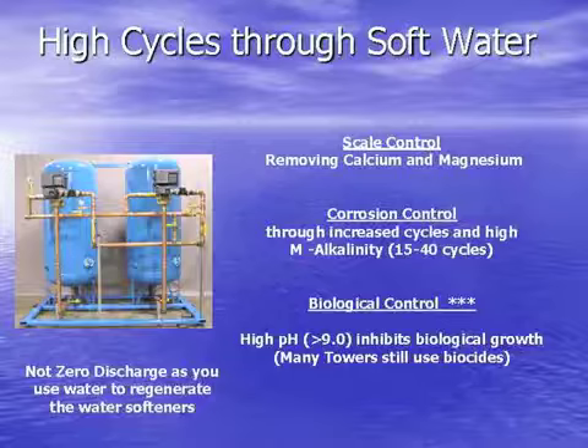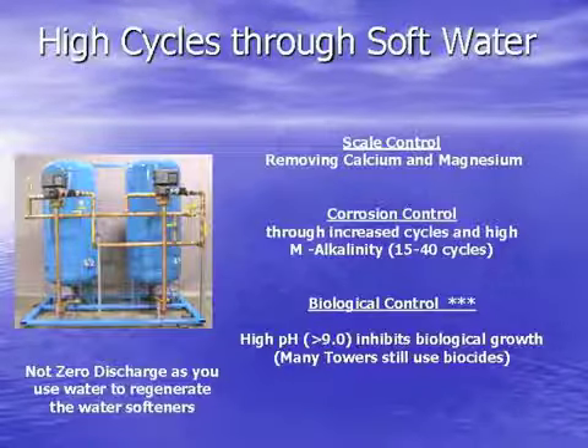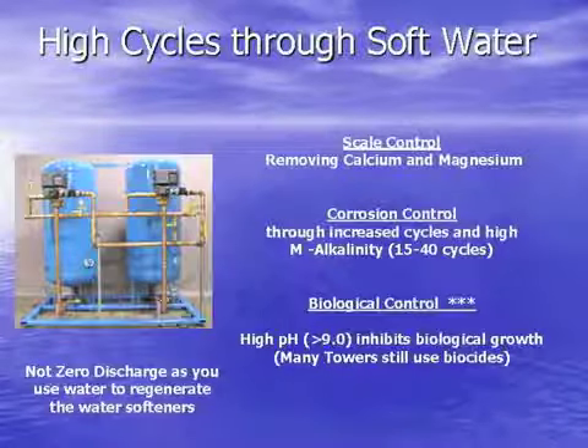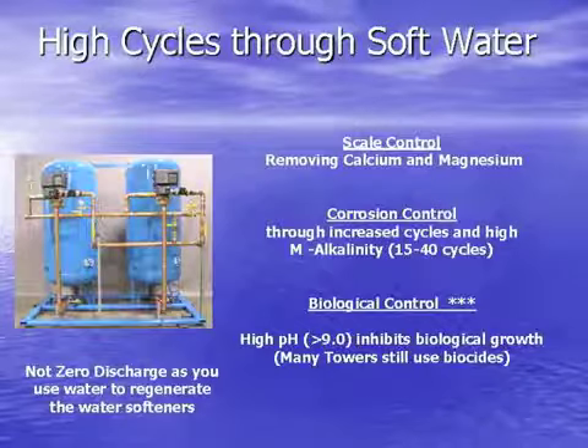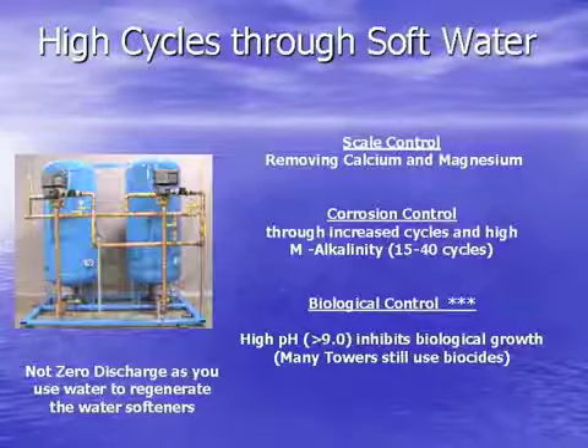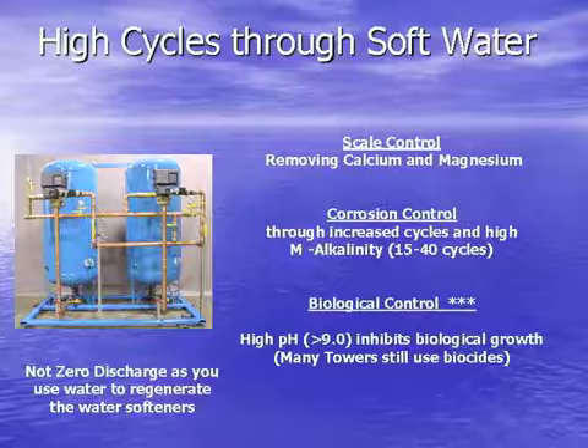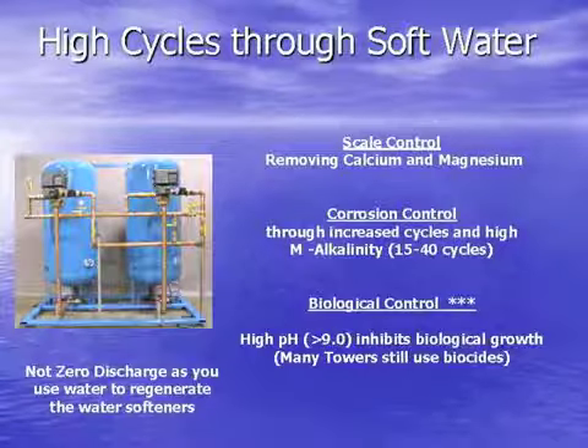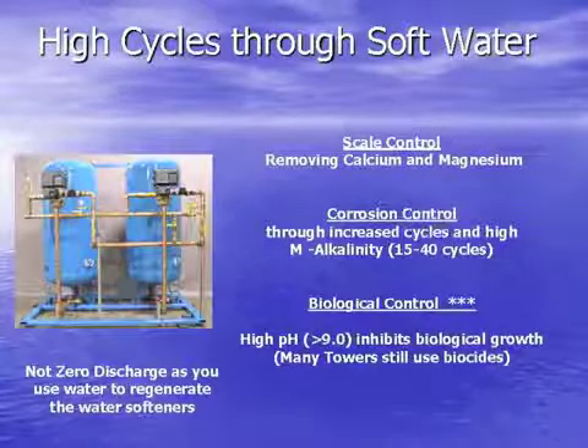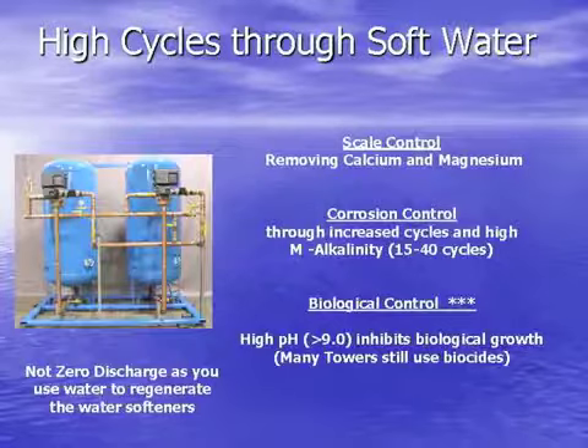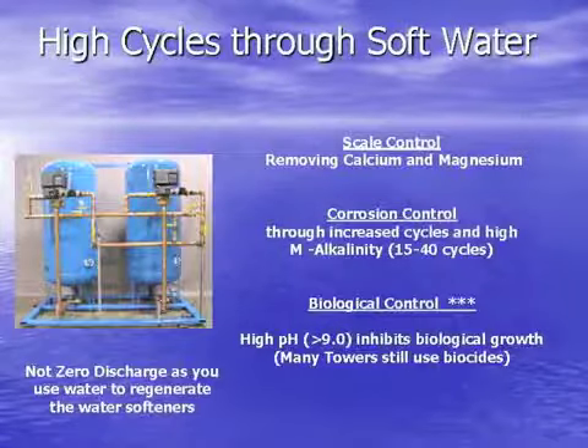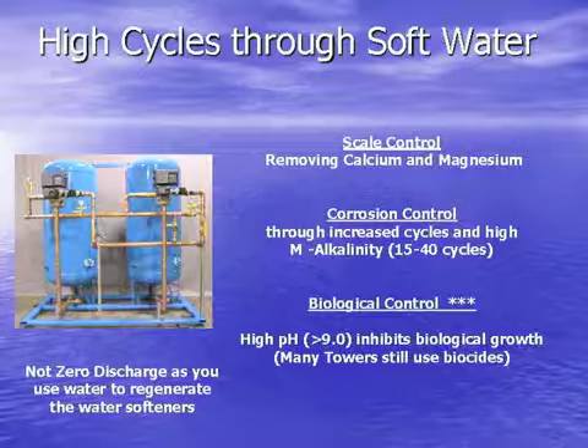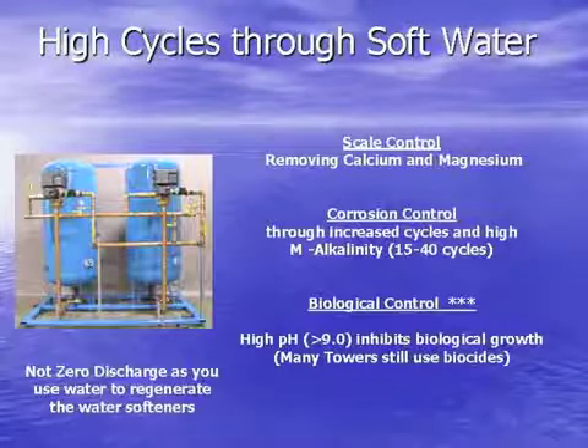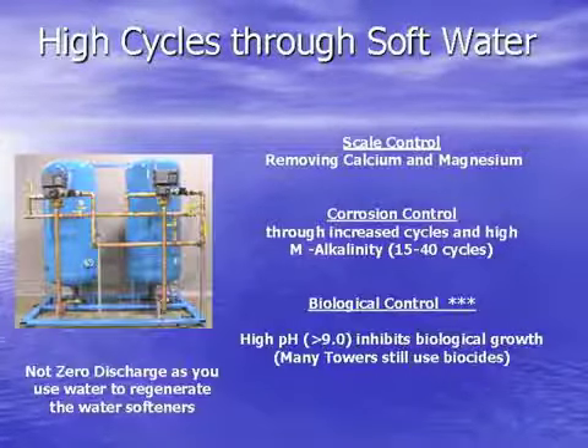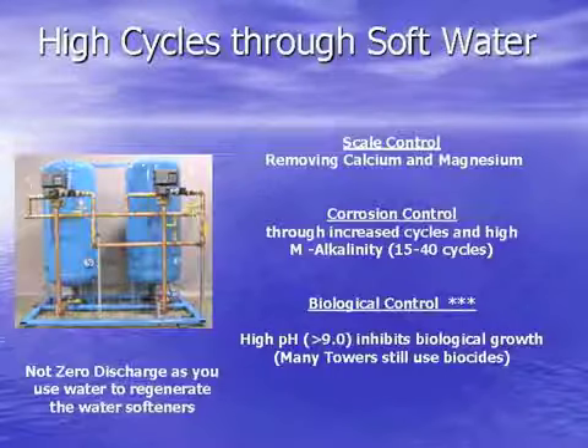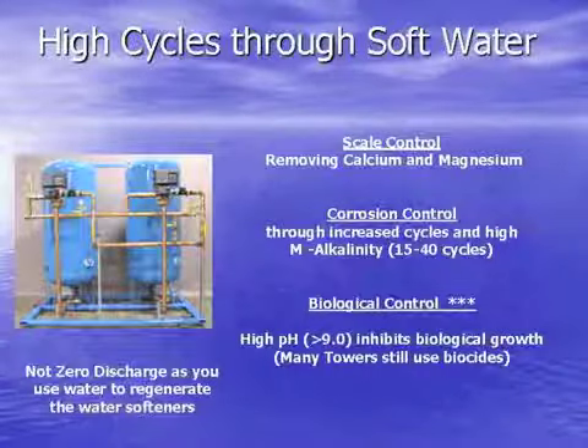We drive the cycles up. Again, we make the water kind of scale forming, but without the calcium. So the high alkalinity in the water and the high minerals prevent the systems from corroding. So that's pretty good. And in most cases, a lot of times they still need to feed some form of biocide around the cooling towers just to control the biological. There are some people that claim that if it's above 9, it kind of inhibits the bacteria growth. And in some cases, we do see some of that in the bulk water, but again, we don't see it on the surface, where there's still questions about that.